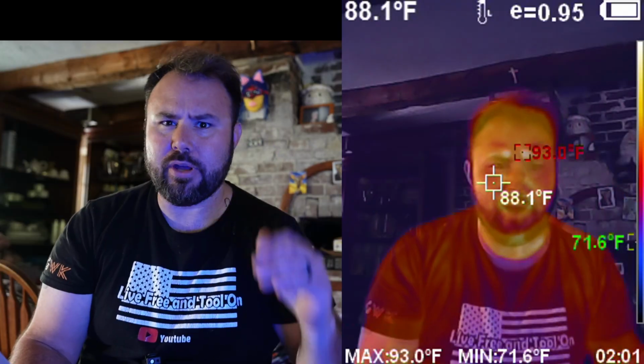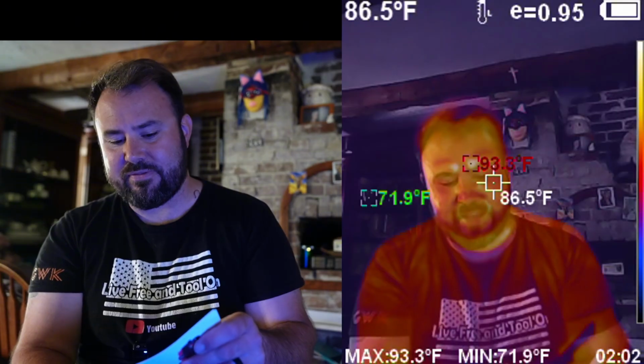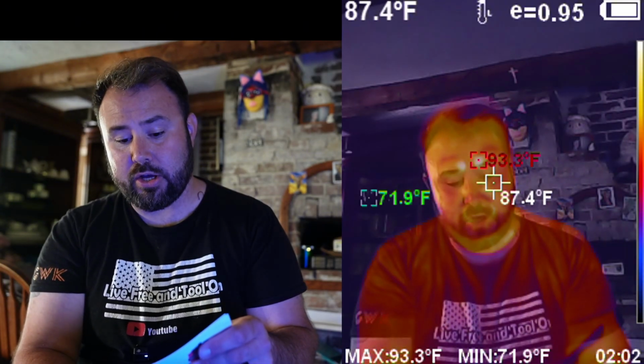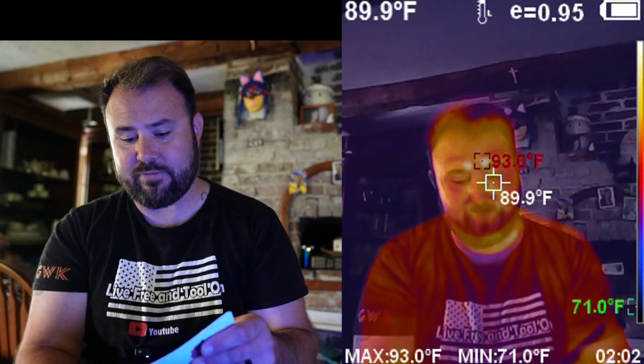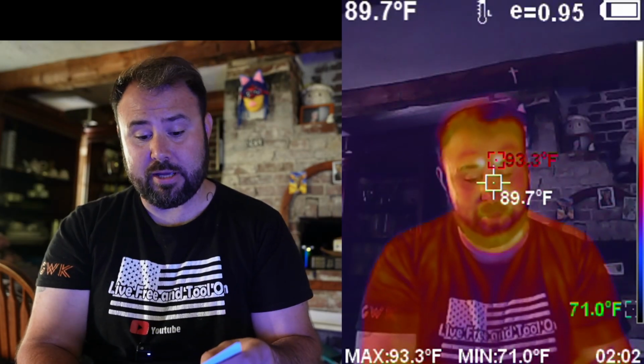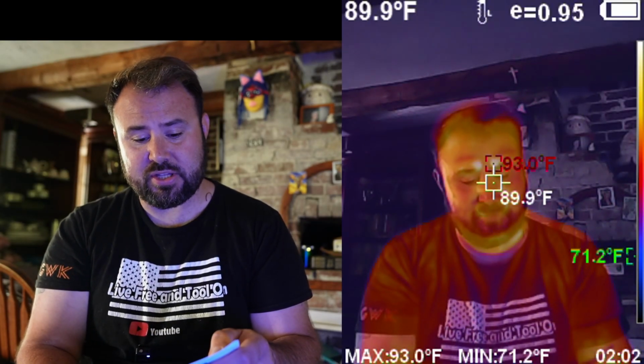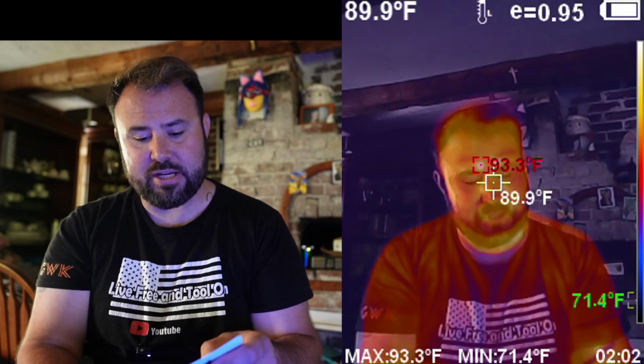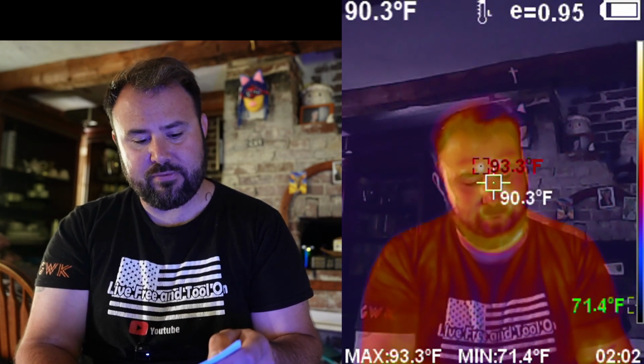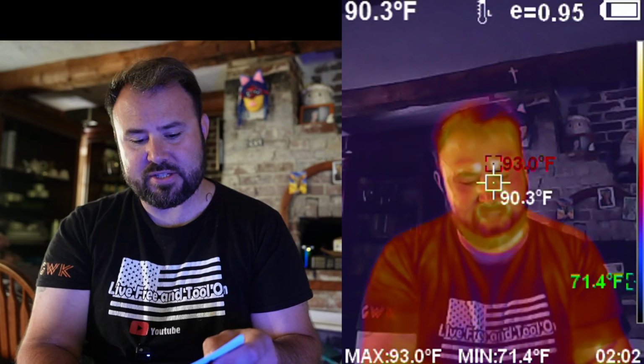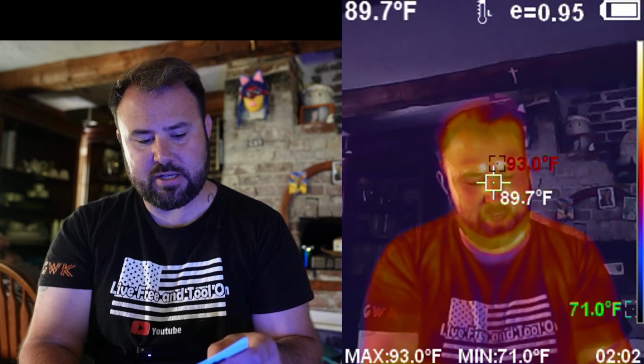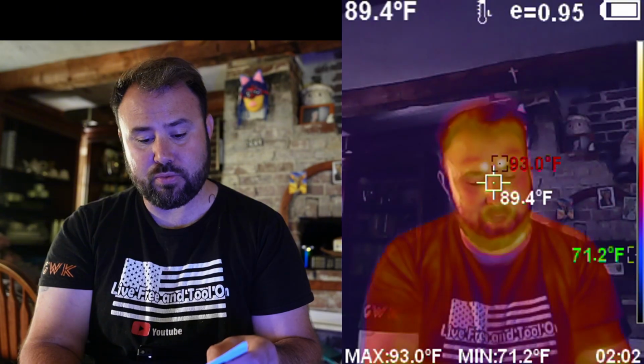Now, one of the things about this particular camera, I'm just going to read some of the specifications because I don't want to miss any, and my old noggin, it's hard to remember all of these. But this is a vanadium oxide uncooled infrared focal plane. The infrared resolution is 256 by 192. And the infrared response range is 8 to 14, and then pixel size is 12.